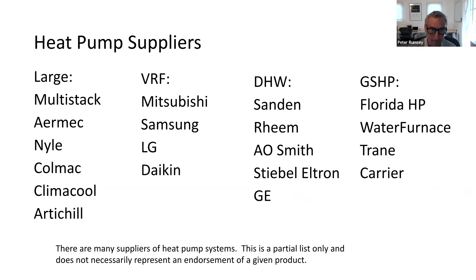I wanted to end this part with a quick reminder that when we talk about decarbonizing and electrifying buildings, we are not trying to use electric resistance heating. Here's an example for a 100,000 square foot building in a moderate climate. The cooling system has a peak load of about 200 kilowatts, and we install electrical infrastructure for that. If we used an electric resistance boiler for the peak heating load in winter, that would require close to 600 kilowatts of heat—a huge impact on the building's electrical infrastructure. With a heat pump system, we only need around 170 kilowatts of heat instead of 590. That doesn't tax the electrical system, doesn't add extra cost or construction, and it also prevents very high electricity bills.